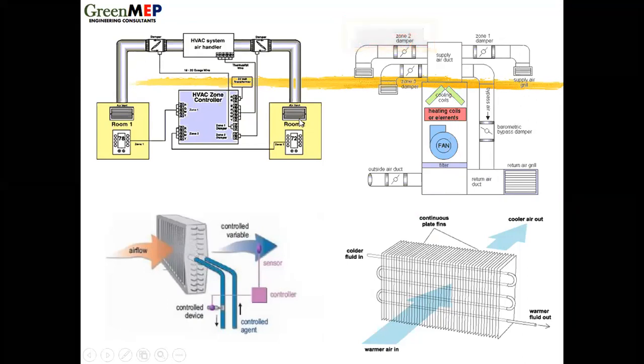And then the user, the occupant in the room, can set the temperature. Right? You can see there's a controller. The controller receives the temperature information from room 1 and room 2, and then it opens and closes the air supply dampers. When these dampers in the air ducts open and close, depending on the flow rate requirement, the fan speed goes up and down, right? If the damper opens, the fan goes up in speed and sends more air, more air per minute, through the cooling coil. The chilled water flows through these cooling coils, all right?